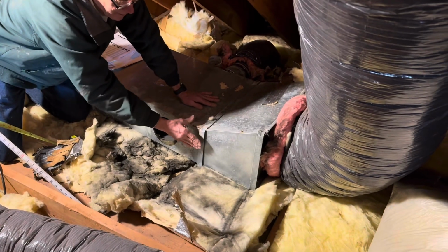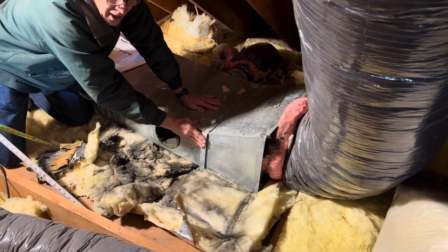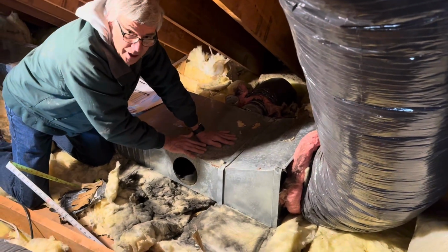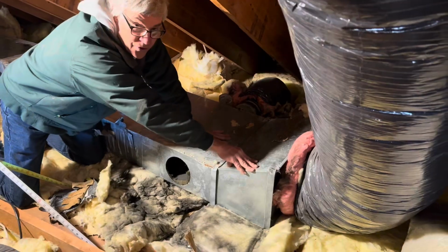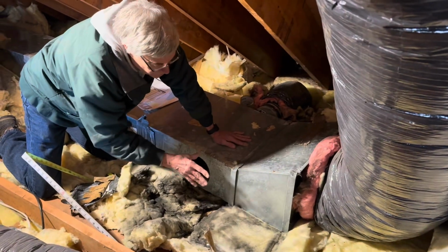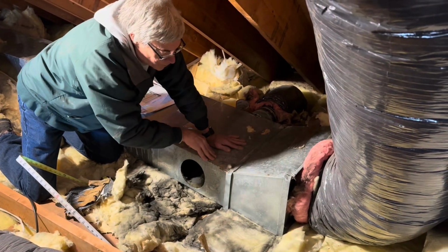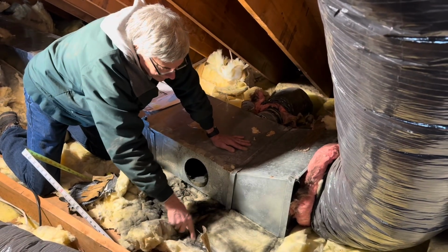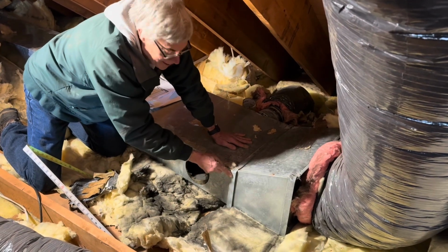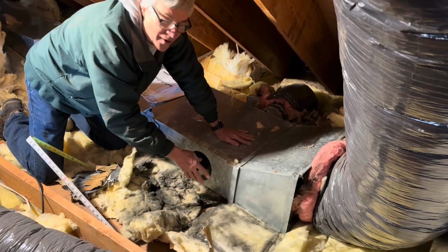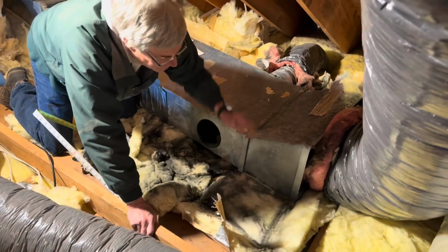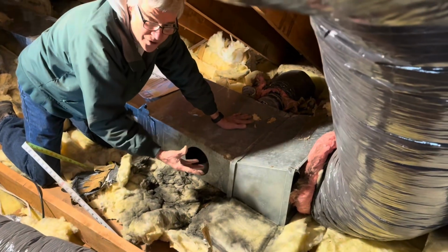This is a drive cleat, and this is a slip. This is a trunk line, and this is a reducer. We're starting with a larger size and reducing it down. And this line that correlates with this drive is an indication of where the air was leaking. And we have another drive over here, and we have another line. So that shows us where all the air was leaking out.